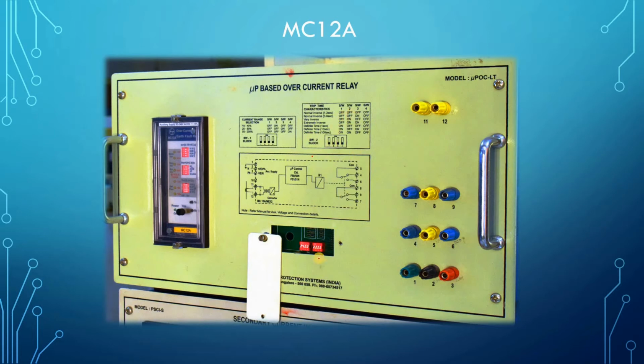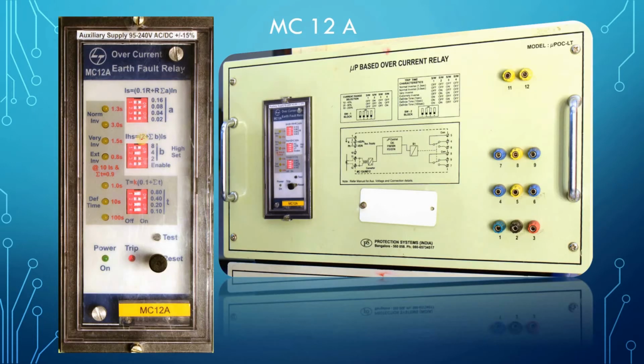So if all switches are off, like it's showing, this one is off and the other side is on, so all are off, that means that is normal inverse 1.3. Right now it is looking like that. So when we perform the experiment, at that time we will set it and see what the characteristic is. And as you can see, R is, let us assume, 1. Minimum R can be 1, maximum R can be 5. So 0.1 can be the minimum IS.